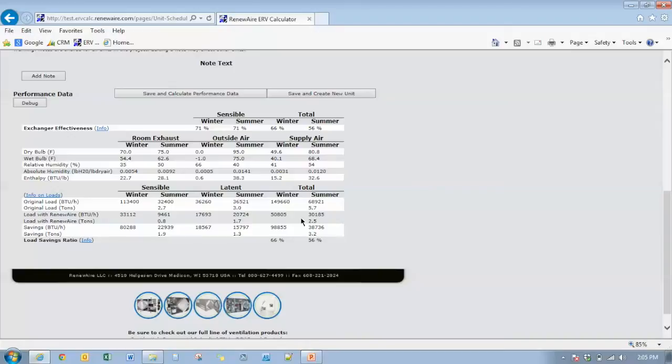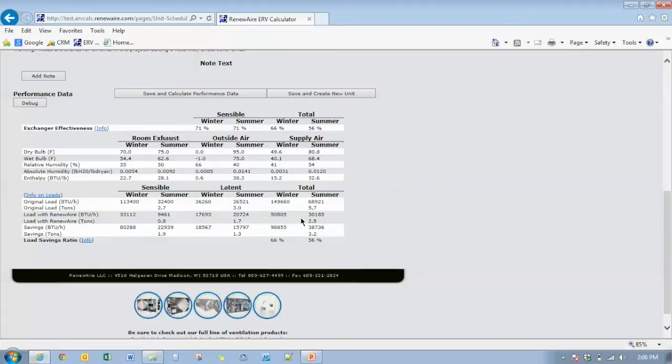Any other outside air sources due to unbalanced air streams would need to be accounted for in the building design through other methods. For example, if you had an outside air hood associated with a rooftop unit that was bringing in an additional 500 CFM to make up for additional exhaust through our unit, that would have to be calculated through other methods other than ERV calc.